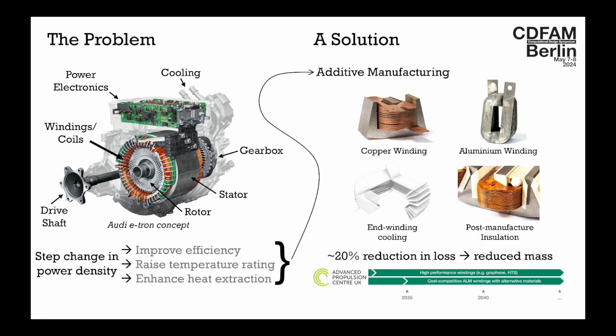However, the initial sizing of an electrical machine is still done using analytical equations, and it works really very well. The problem, though, is that some of the choices you make are down to the designer, and they're typically based on experience, but also on bias. If you've spent the last 20 years designing permanent magnet synchronous machines, every electrical machine problem - the solution is a permanent magnet synchronous machine. I can guarantee it.